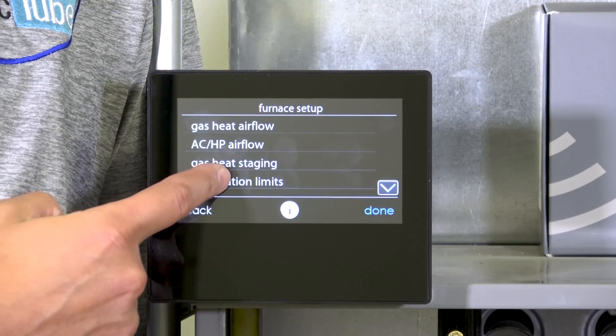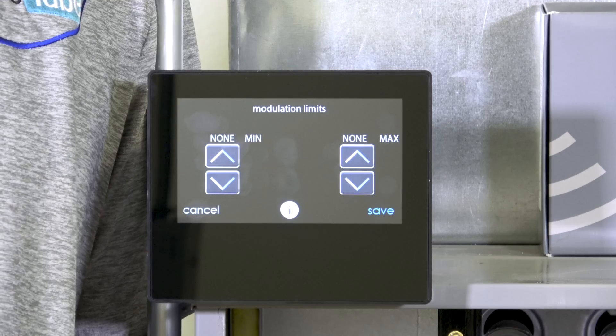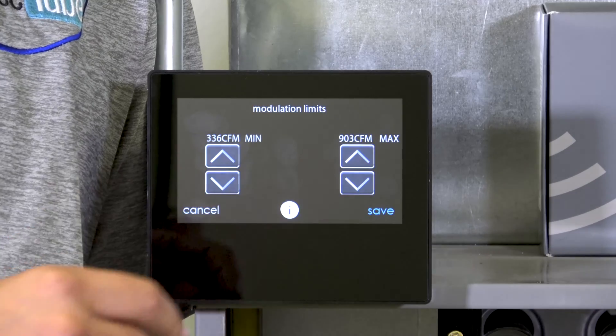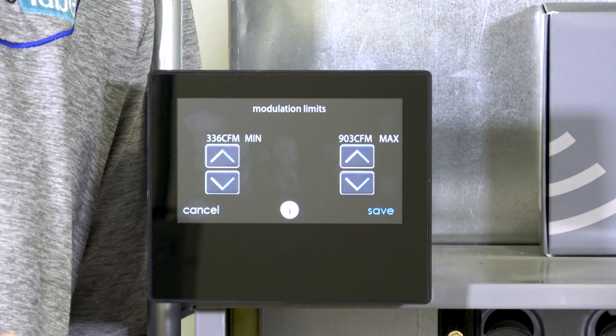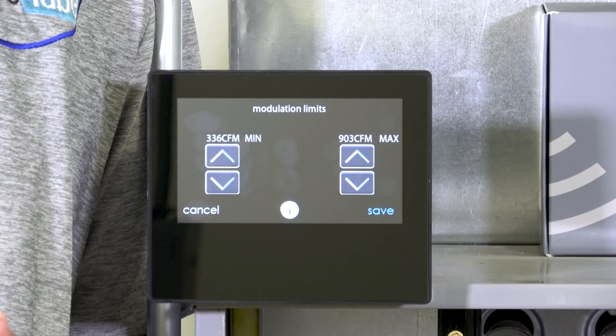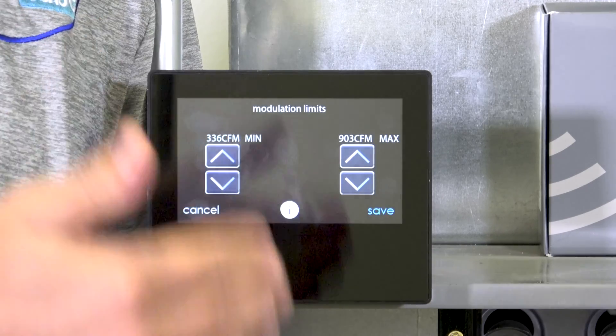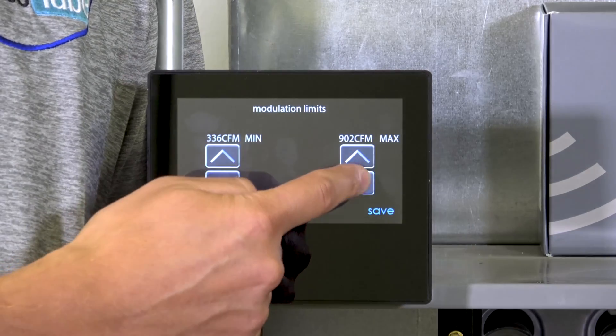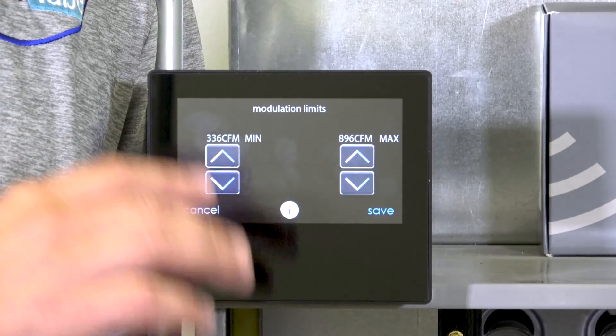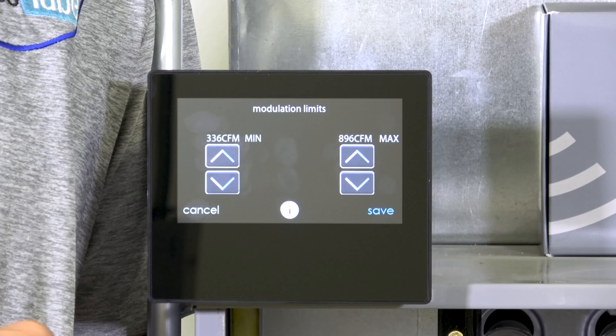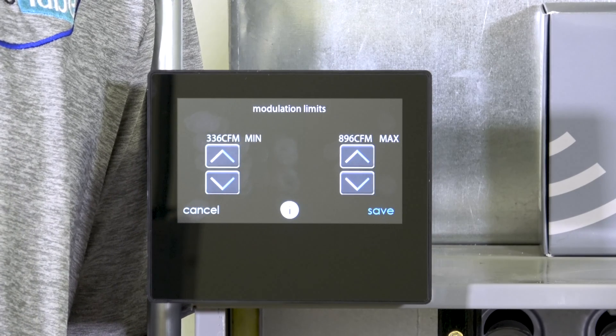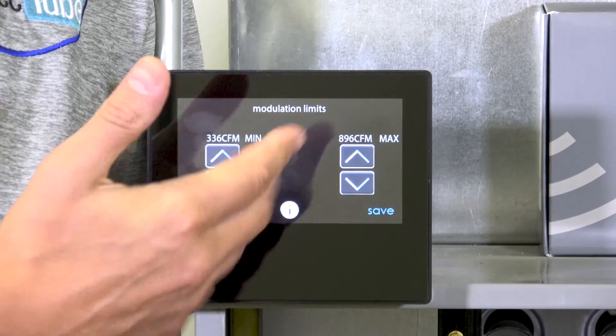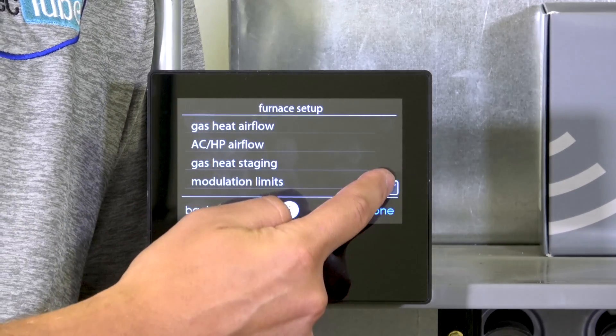Modulating limits — on modulating gas valve furnaces only you'll see this screen. I can chop off the lower or higher limit of the gas valve, which modulates from 40 to 100 percent in 1% increments. For example, if I installed a 100,000 BTU furnace but only need 90,000, and 80,000 wasn't enough, I can buy the 100 and throttle it back. The way this works — somewhat unusually — is by throttling CFM rather than directly throttling the percentage, which indirectly throttles the gas valve.